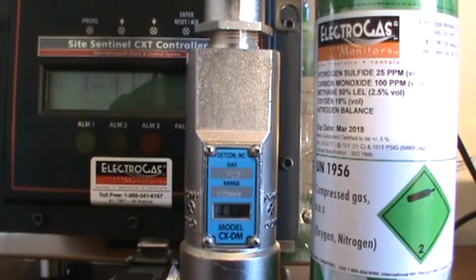There are 3 different ways to perform a bump test with your H2S CXDM sensor. The first way is called a full function bump test, and the goal of this test is to challenge the sensor with a known concentration of gas and to confirm the sensor sends the proper signal to the display on the sensor, as well as sending a proper corresponding signal to your CXT controller display, and that your controller also will now send a proper signal to any external alarms or annunciators configured with this sensor.